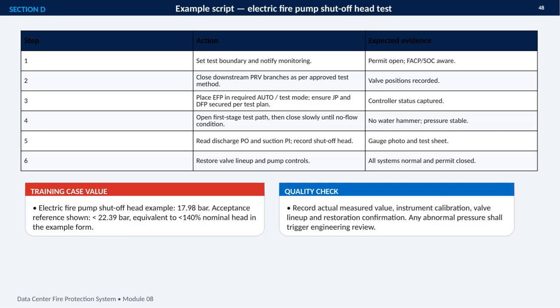This section presents an example script for an electric fire pump shutoff head test. The sequence is designed to control the test boundary, protect the system, and create clear evidence at every step. First, the permit is opened and monitoring personnel, including the FACP and SOC, are notified. Next, downstream PRV branches are closed according to the approved method, and the valve positions are recorded. The electric fire pump is placed in the required auto or test mode, while the jockey pump and diesel fire pump are secured as defined by the test plan.